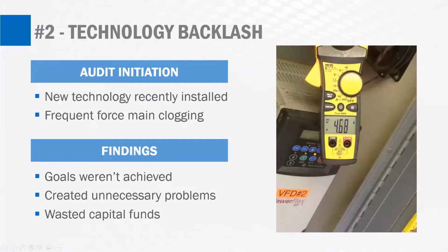For the second case study, this involves new technology being implemented on pump stations. There's a lot of technologies out there that can be utilized for pump stations, from controls and SCADA. There's a lot of new technologies that are continually coming out for pump stations. In this case, the technology was variable frequency drives, or VFDs, that are used to control the motor speed and thereby control the pumping rate for that pump station. In this case, the VFDs were implemented with the goal of achieving electrical savings.